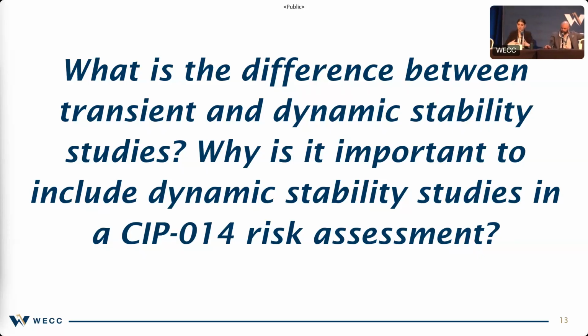You may end up having a collapse of a magnetic field — if you're familiar with core concepts of electromagnetic theory, if you've got current going through a line, you've got a magnetic field around it. If that collapses, you have to start that system back up from scratch, and it's probably not going to connect appropriately. You end up with a larger gap in time delay getting reconnected — it essentially trips. So transient studies are really looking at more localized, immediate impacts, on whether or not nearby elements are going to stay in sync and not trip.